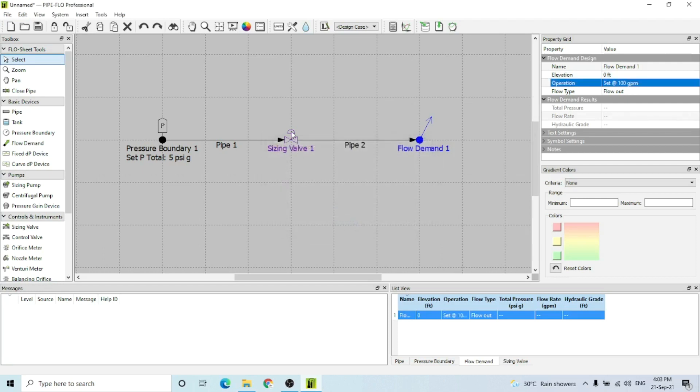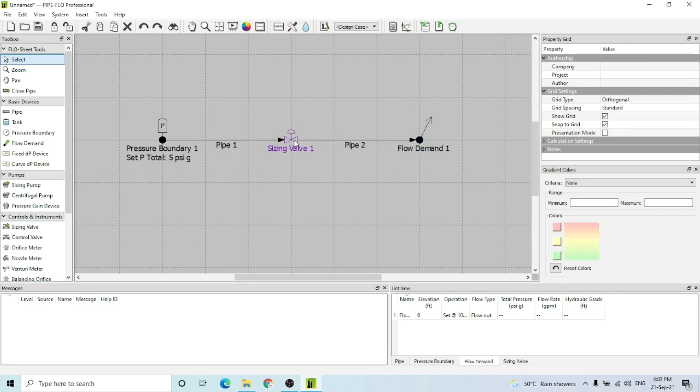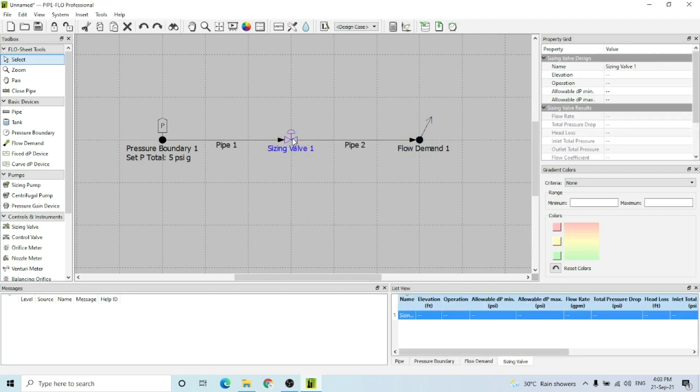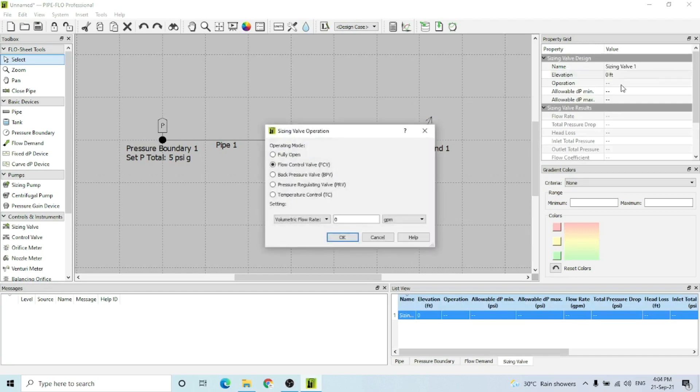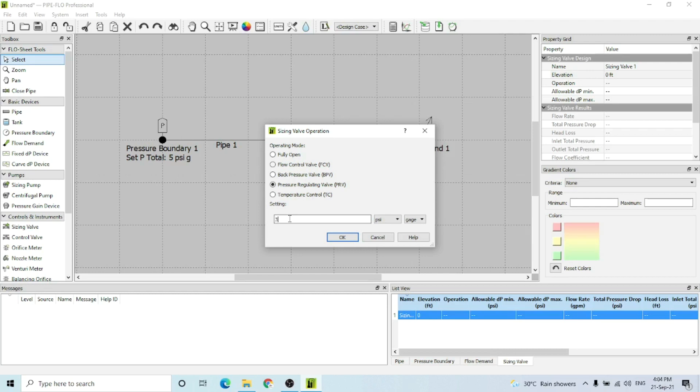Now going back to the sizing valve, I have to select the elevation which is zero again. For the operation, I'm going to size the pressure regulating valve, so I'm selecting a pressure regulating valve. Then you select your desired pressure that you want to regulate - let's say it is 3 psi.